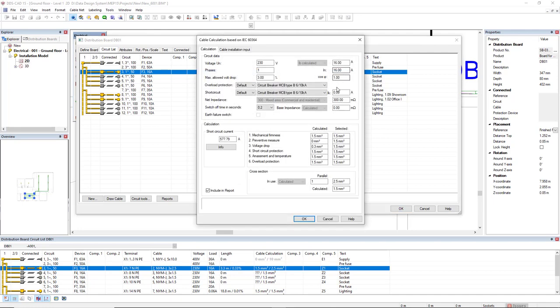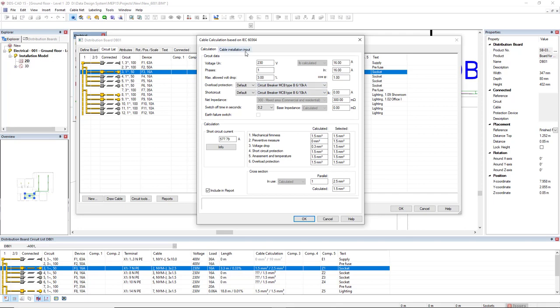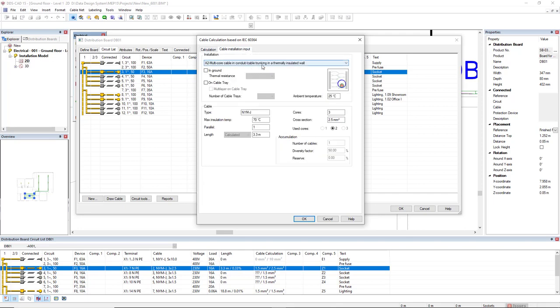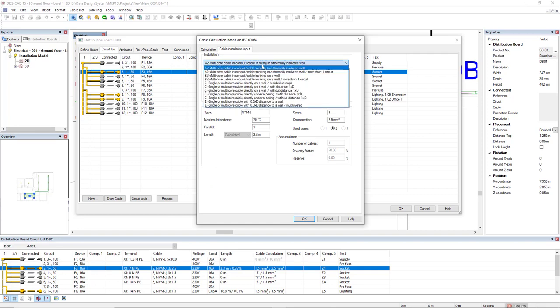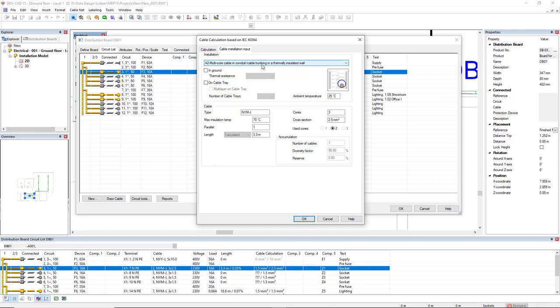So, we see here the cross section for the cable. It is selected at 2.5 mm², but it has been calculated for 1.5 mm². Here we have the parameters saying that 1.5 mm² would be OK for it. If you would like to change the cable type installation, we come to the tab cable installation input. And you have several options here to change the installation type such as could be also in ground or on cable tray.